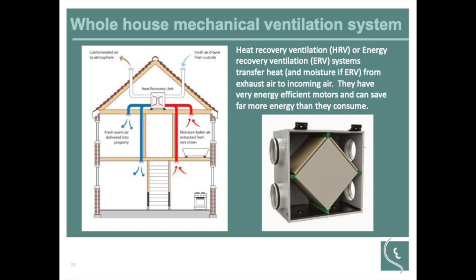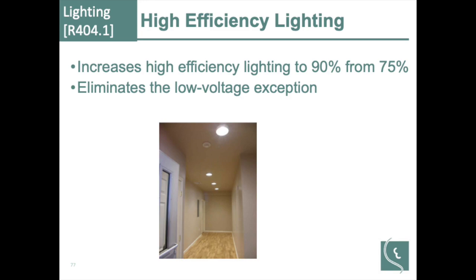So an HRV or ERV can provide some benefit by using that crawl space as a negative exhaust and pulling that air out. It's a lot better than the common practice I've found where they cut a hole in the return duct and then on the far side of the crawl space they just drop a supply in. And then you're pulling that nasty crawl space air into your return and blowing it through the whole house.